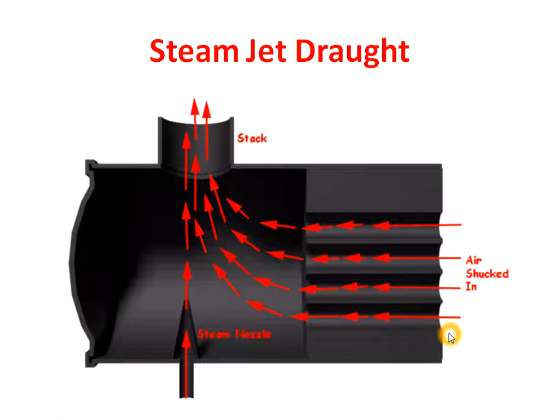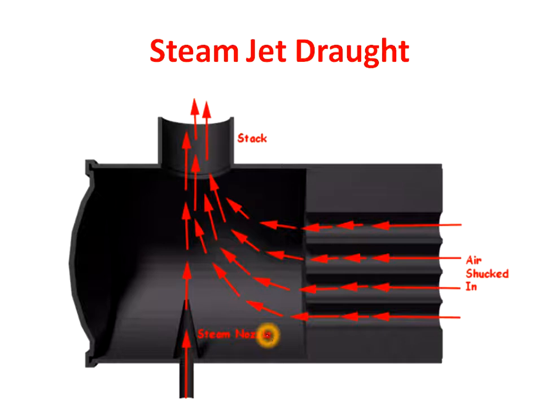Its major disadvantage is that when we are starting the boiler, the boiler doesn't have any steam pressure. So at the start we can't produce draft with the help of this steam nozzle, because in the beginning the boiler doesn't have any steam pressure. Only when the boiler generates sufficient steam pressure will this steam jet draft system work. So this is its major drawback.